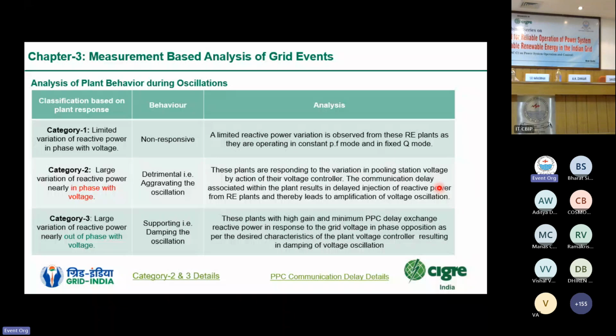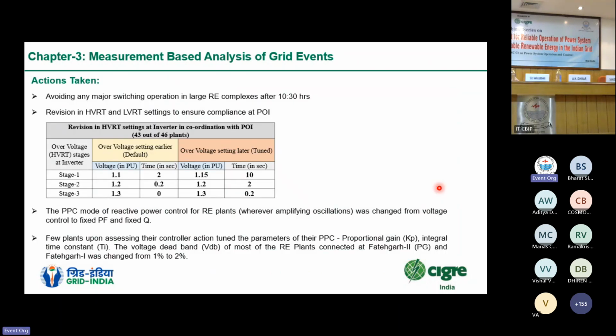Then we had some category 3 of RE plants where the large variation of reactive power was out of phase with the voltage. So say voltage was increasing, then plants were reducing their injection or increasing their absorption of the reactive power. So thus they were trying to control the oscillations and smoothen out the voltage profile. Then from the measurement based analysis, we were able to arrive at certain conclusions, like to implement certain measures in the operation horizon, so that these oscillations can be mitigated, or the instances can be minimized.